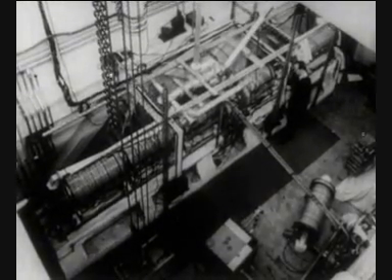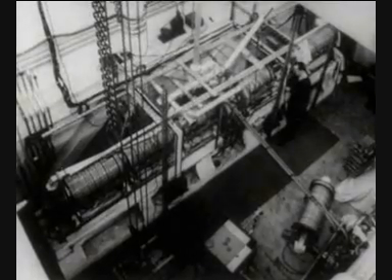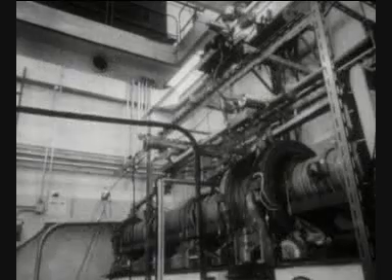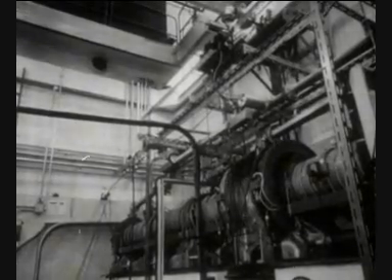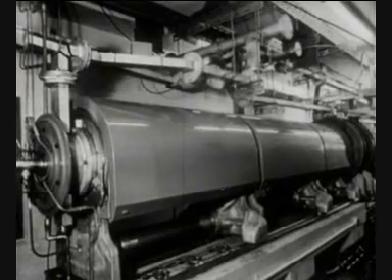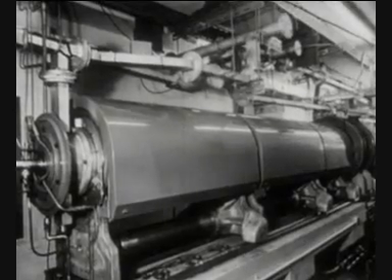This latter type of equipment is known as the traveling wave linear accelerator. This machine provides a silent, compact, high-intensity source of X-rays for therapy and nuclear research. Now let's see how it works.